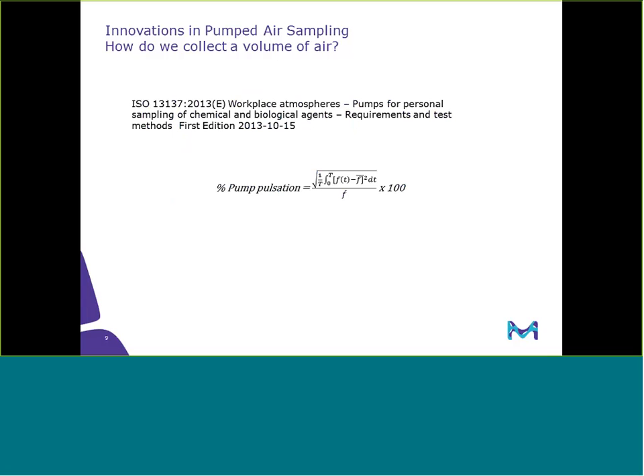And here's talk about pulsation. Here's the ISO 13137. They define pump pulsation as a percent. Mathematically, it's the percent ratio of the area between the pulsation wave and the mean flow, volume flow for a given time period. So for those of you who enjoy math, that's kind of fun and interesting, but this can easily be programmed into an Excel spreadsheet, and that calculation can be performed. That will come up again in a bit.